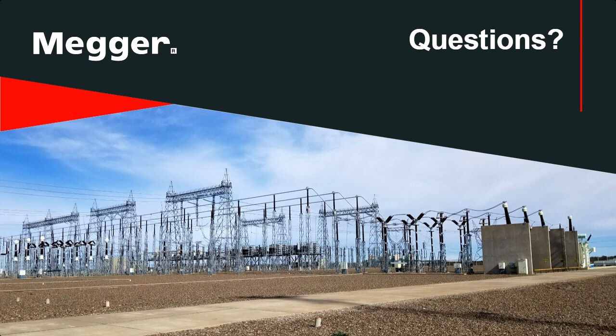What equipment do you need to perform DCM testing with the TM1800? So for the TM1800, the only thing you need is a separate device. It's called a DCM 1700. It goes in line with the TM1800, and that allows you to do that DCM test, that dynamic capacitive measurements test.